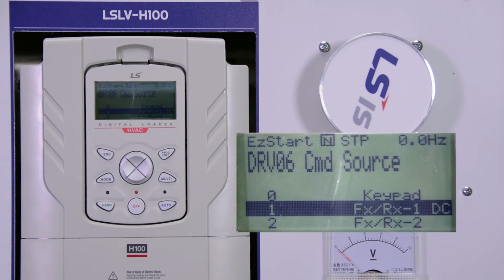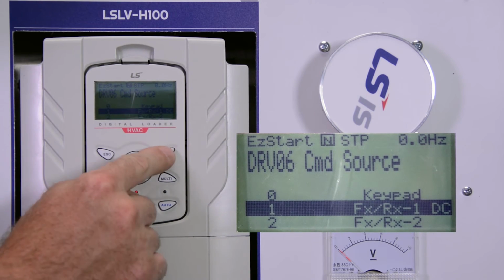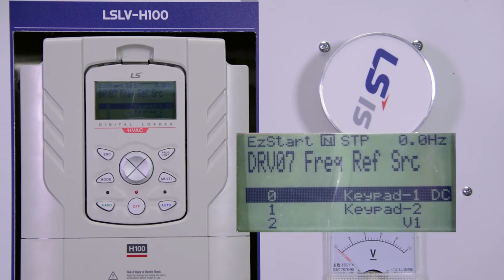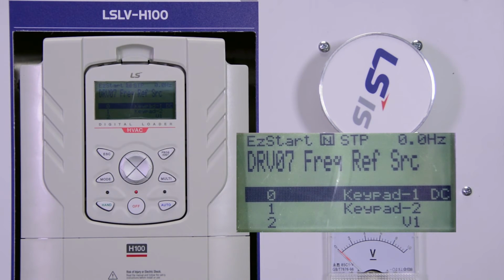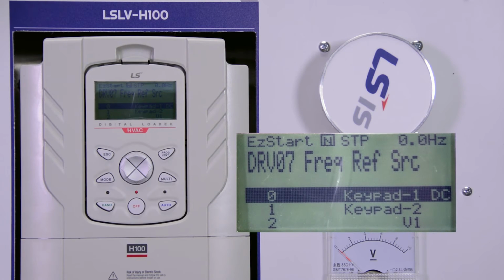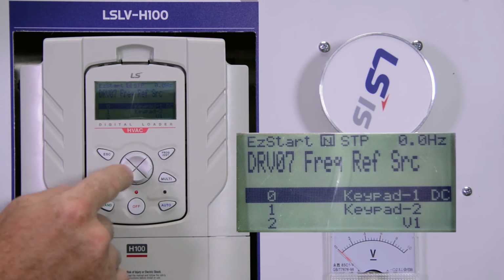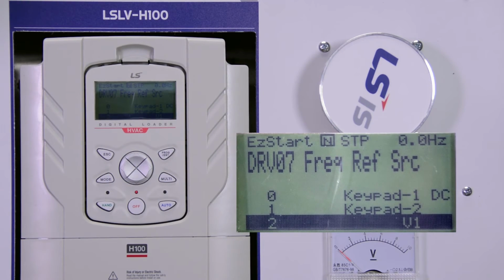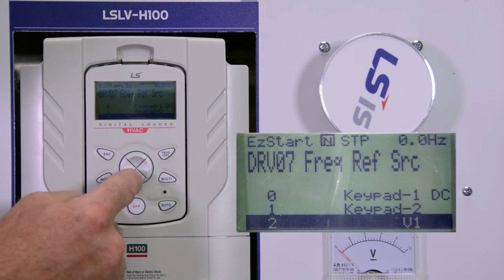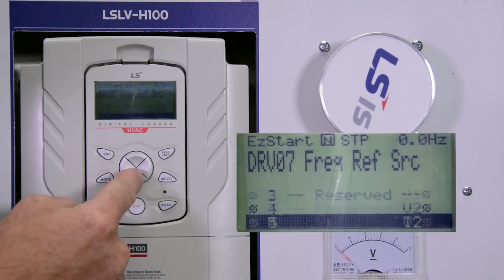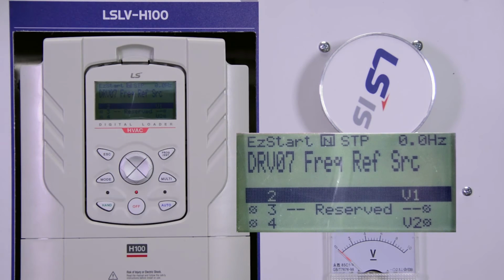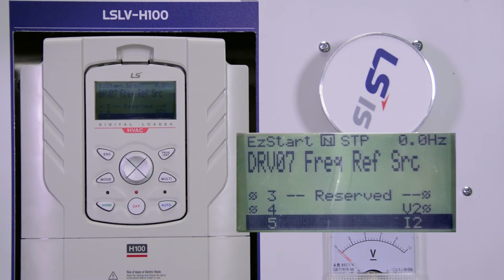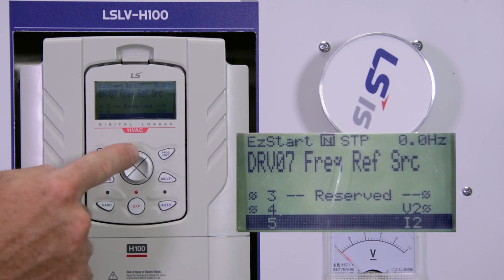And the next question is, how do we want to start and stop the drive? The command source. We are going to start it with the digital inputs, FX RX1. We'll leave it there. Next question is, how do we want to control the speed of the motor? So, frequency reference source. And that we will just leave at the keypad for this demonstration. If for some reason you needed to change to an analog input speed pot, you can change to V1 or I2. V1 for 0 to 10 volts and I2 for 4 to 20 milliamps.